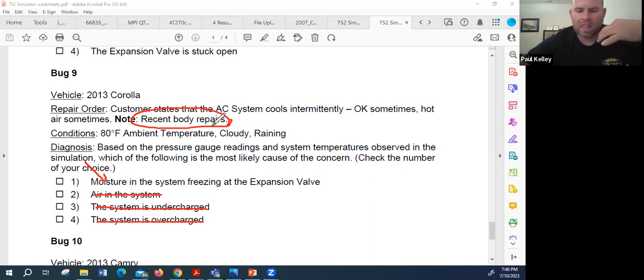And this is where it gets a little tricky. I thought that would make the low and the high rise, because it's a restriction, and I think it would at first. But how is the compressor going to make a high side if it's not pulling any new refrigerant because it's so restricted? So I tend to agree—I think it would definitely draw the low side very low, if not into a vacuum. It might at first make the high side too high, but then I think it would make the high side too low because the system's so restricted it's not sucking up enough refrigerant to build high pressure. That one I struggled with a little. Now, why does it all of a sudden normalize?